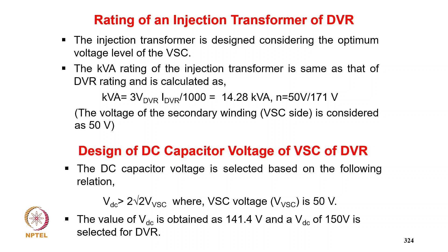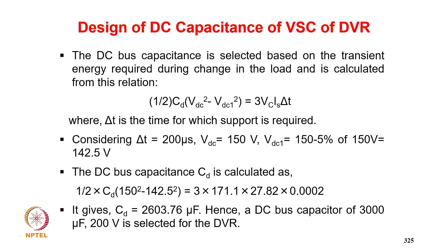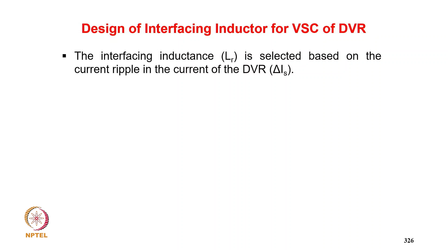Design of DC capacitance of VSC of DVR. The DC bus capacitance is selected based on the transient energy required during the change in the load, and calculated as half CDC in bracket VDC square minus VDC1 square equals 3 VIS delta T, where delta T is the time for which support is required. While considering delta T equal to 200 microsecond, VDC 150 volt, VDC1 150 minus 5% of that is 142.5 volt, the DC link capacitance calculated by putting the values comes to CDC equal to 2603 microfarad, and a DC bus capacitor of 3000 microfarad at 200 volt is selected for the DVR.